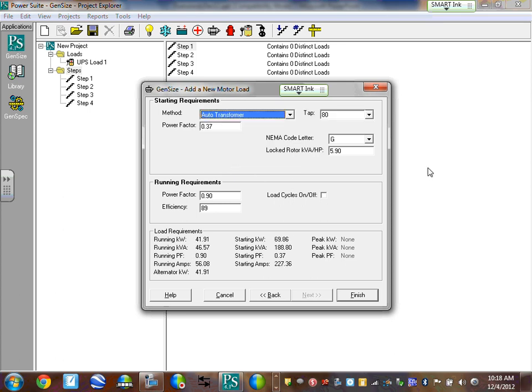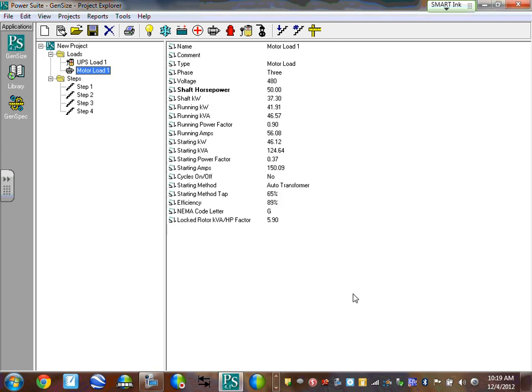Auto transformer, you'll see a lot in municipalities running big pumps at water departments and so on. Mainly use a 65% tap most commonly. That reduces the starting power factor, which is the concern here. Get that motor running for pumps. So we'll put in a 50 horsepower with that on.